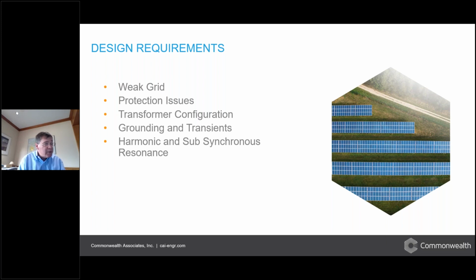And then last but not least, this we know is a huge area, is harmonic and subsynchronous resonance studies. These are typically EMTP studies. The subsynchronous resonance can be broken down into concerns with series compensated lines. So for example, in New Mexico, you have a bunch of series compensated lines that interconnect between basically the Albuquerque area and Navajo. In Texas, from West Texas into Central Texas, Dallas, and then down into Houston, there are series capacitors, and they're concerned about what happens with the subsynchronous resonance.